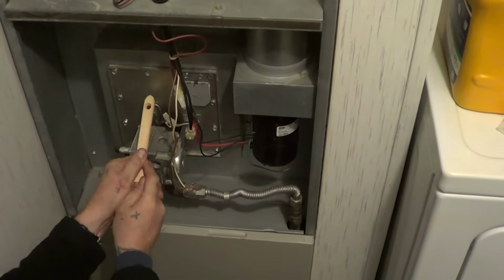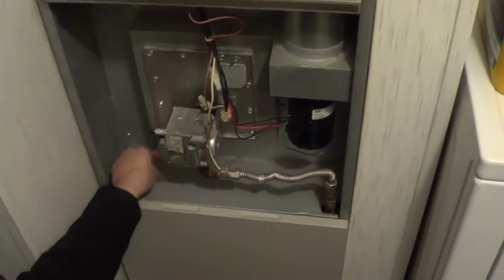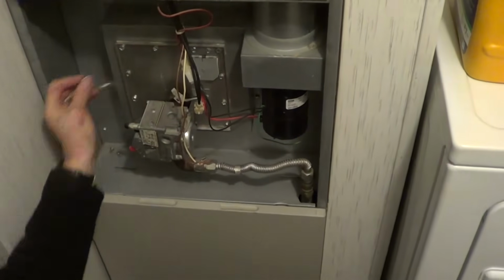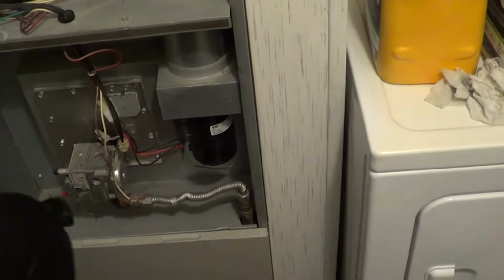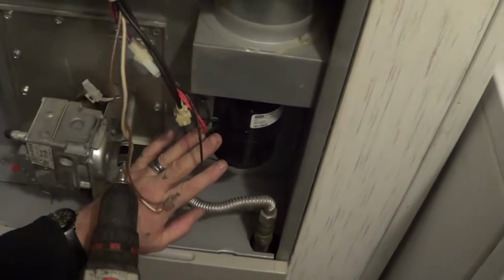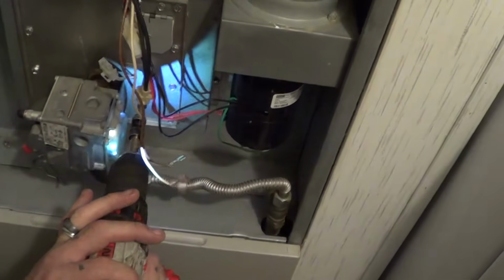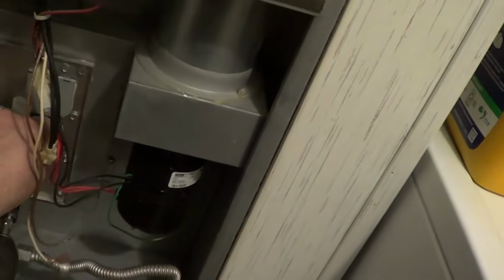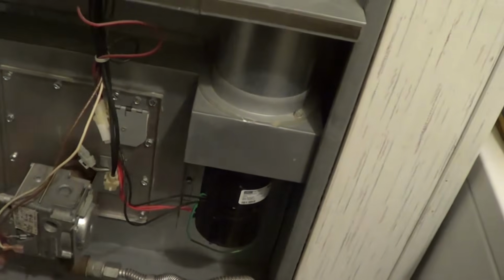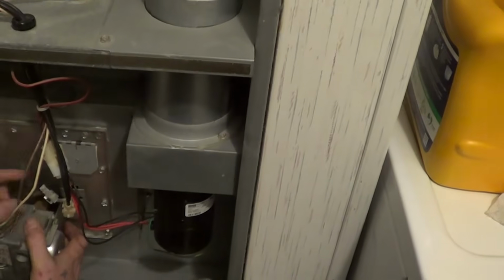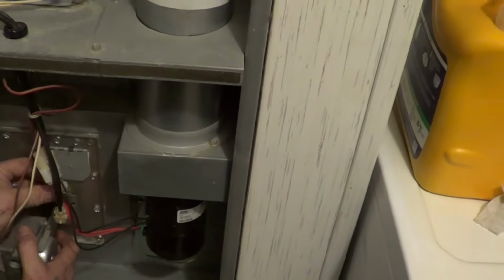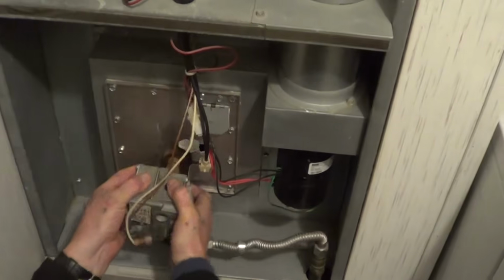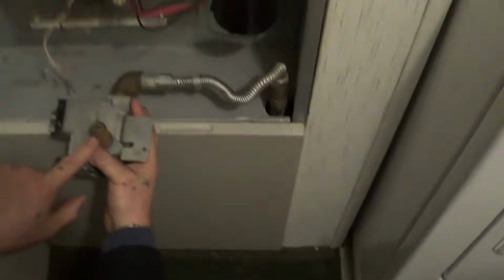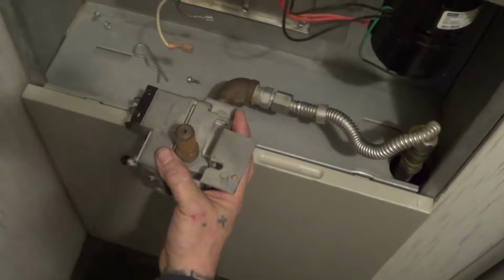So we'll pull this out right there. You can see this pin comes right out of there. And right here, this one is a 1/4 inch. So this little nut right there will come off first. Okay. And then this comes straight out, so we wiggle it a little bit. Make sure you don't get this caught there, put that to the side, and just pull it out. And again, we have the orifice there, and we can check for spiders and things in there.